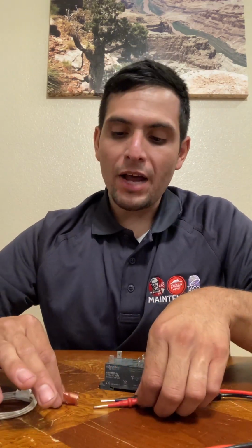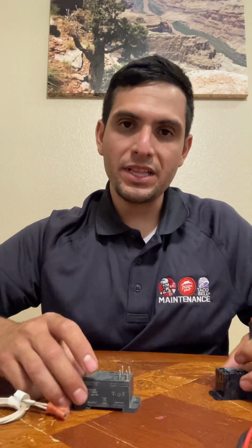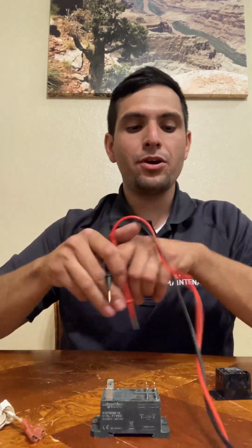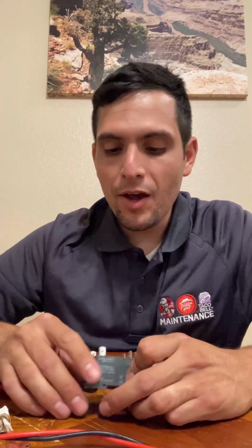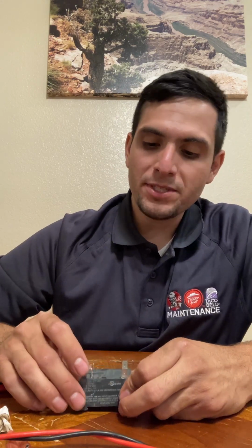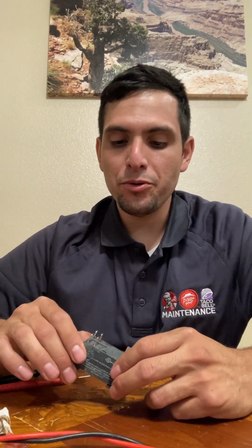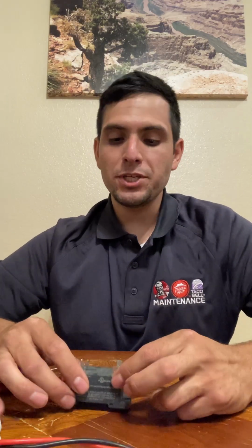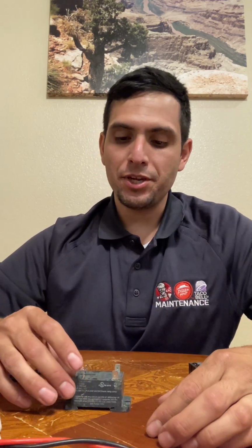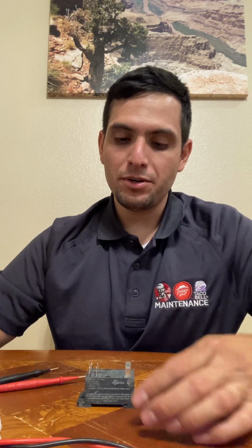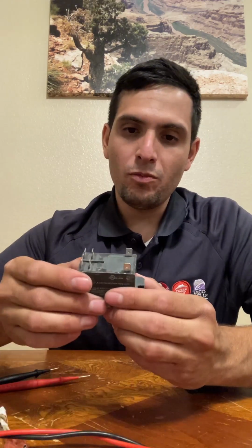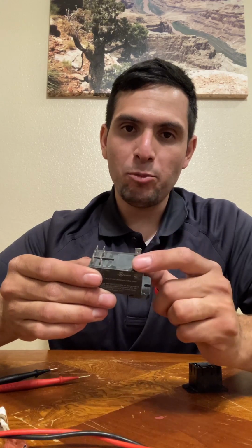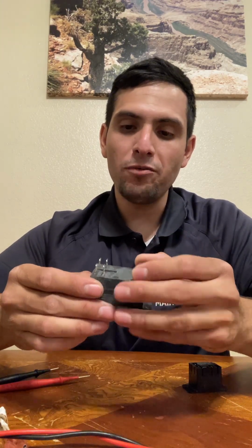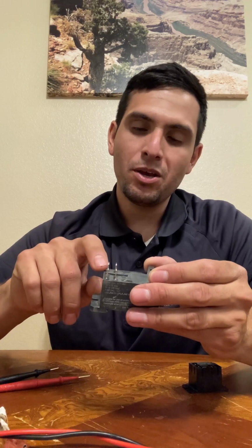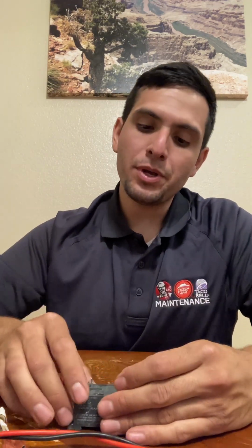Then from there, I would go on to the relay. I'll start with this style relay. You can look on there and it'll map it out. It'll show you which terminals are normally open, which are normally closed. It'll usually have some kind of indication of which one's your control voltage and which one's going to be your actual 120 volt. So your control is obviously going to be coming from the board, and when it gets the right control voltage, that's what tells this relay when to open up and feed power to your heating element.